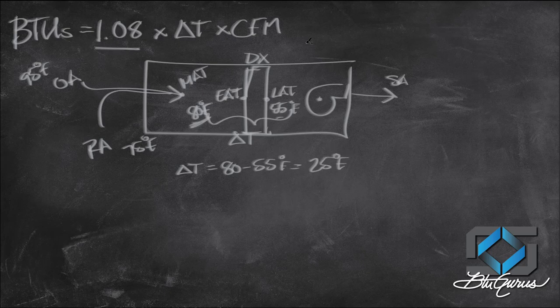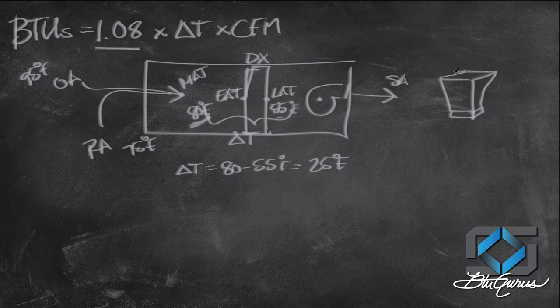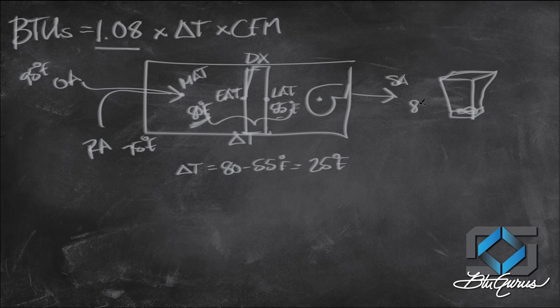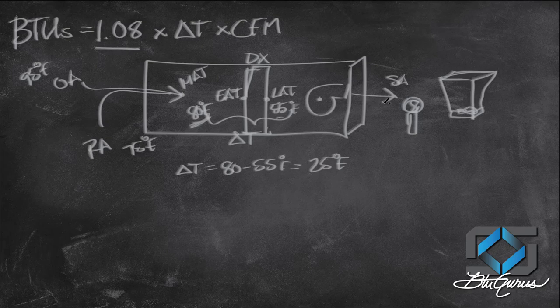Then there's another thing in here, my CFM. A lot of times if you're an air balance guy, you can calculate this or measure this using some sort of hood that is calibrated. You can take this venturi and measure an airflow. Sometimes people use this really simplistic, more of a guesstimate than anything, but there's a device that can sit there and measure airflow and then you can calculate that through the cross-sectional area of whatever you're measuring to get a CFM.